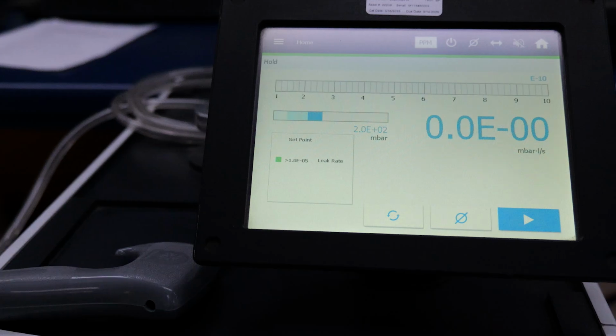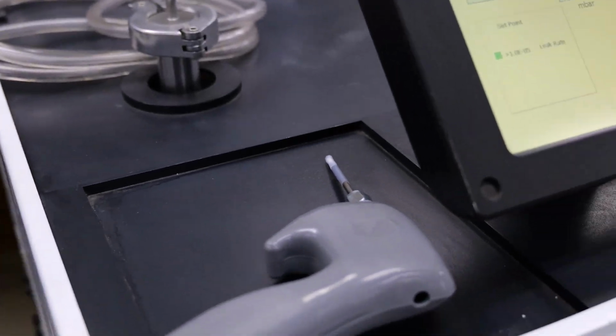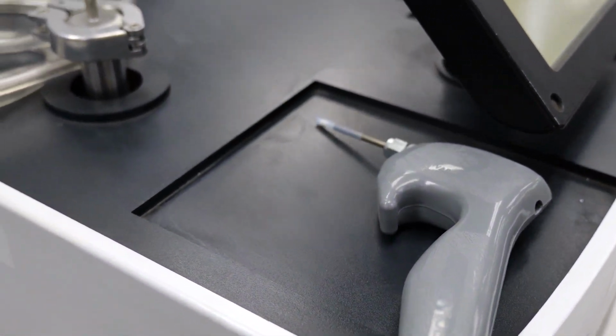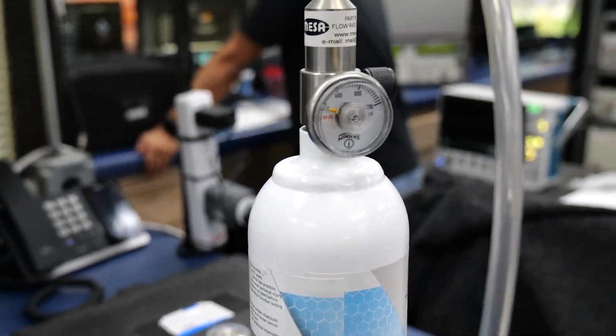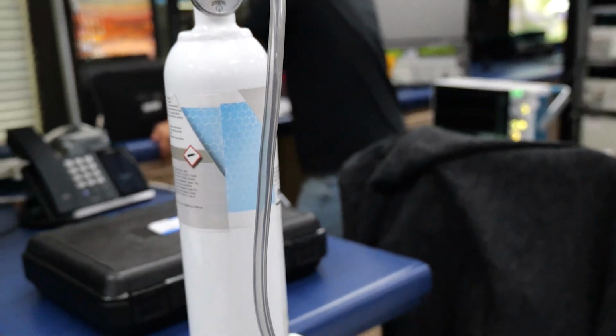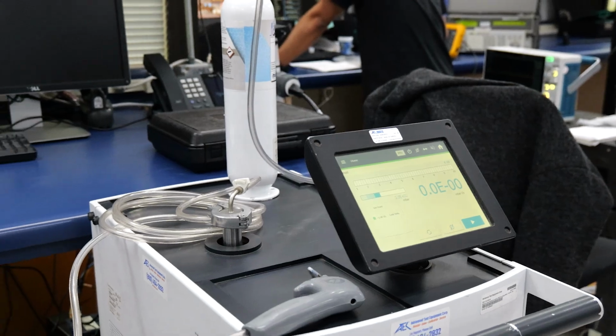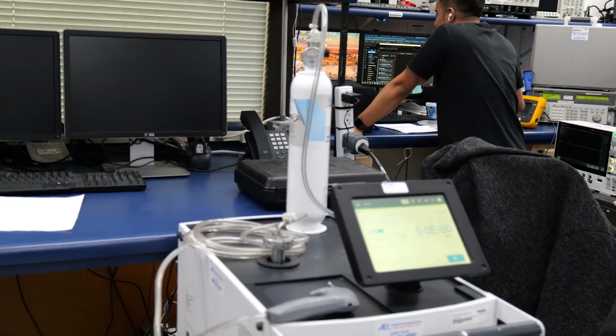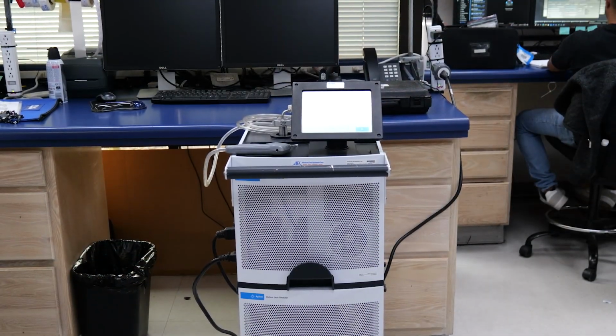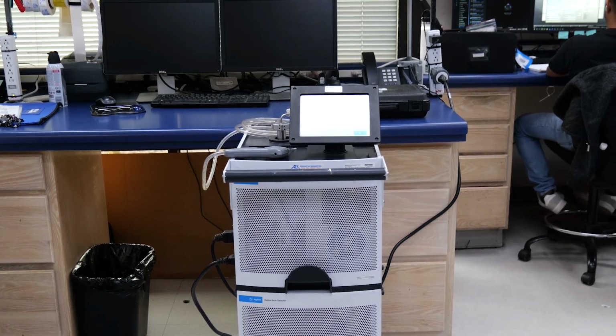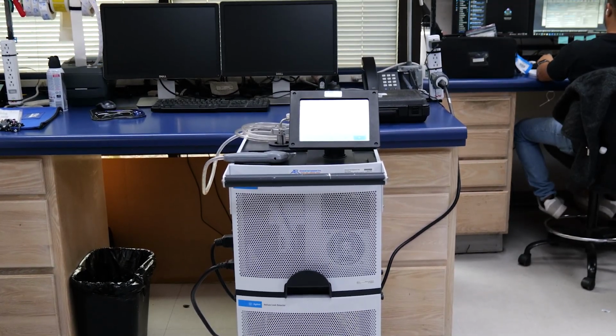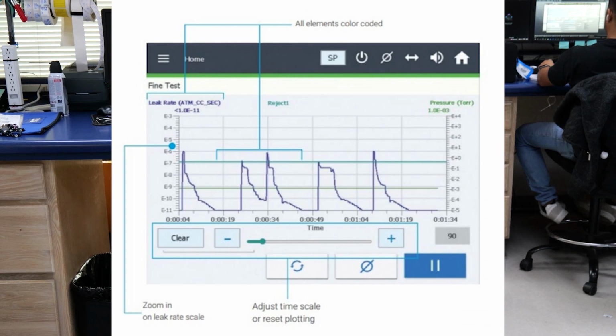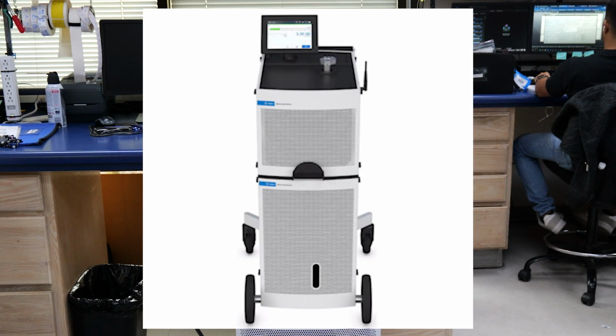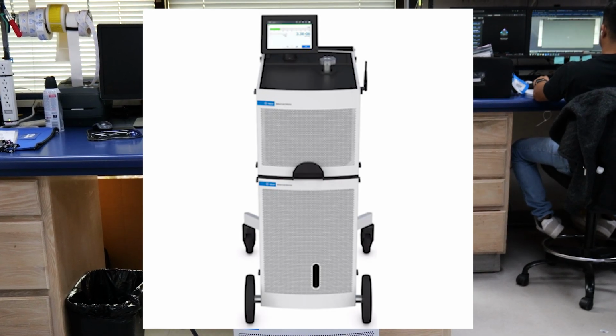Looking more specifically at the HLD 15, this unit has a dry scroll pump, meaning an oil-free pump, which is a lot less maintenance. You never really have to fill in any oil. The pump is pretty much set to go right from the start. This unit also has an interface remote control, which is helpful for automating tests, and a discrete I/O interface, so you can remotely start and stop sequences, and it supports custom sequences as well as automating tests.